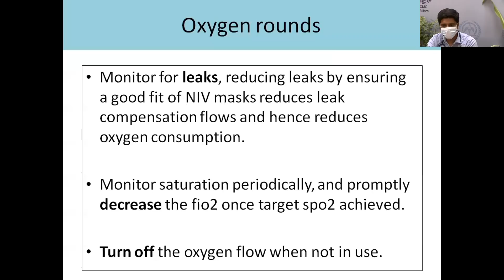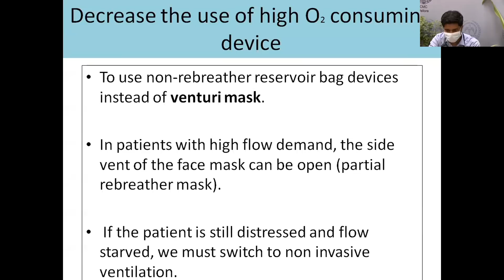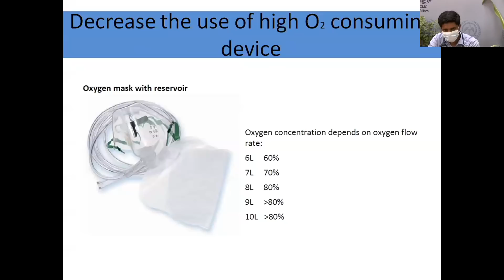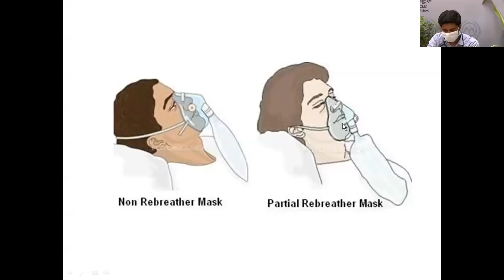So we have moved on from the Venturi mask, which is a high oxygen consuming device, to a non-rebreather reservoir bag device, where with a flow rate of 6 liters we can achieve 60% FiO2, as compared to the Venturi mask, which will require a flow rate of about 15 liters. In patients with high flow demand, the side vent of the face mask can be opened up so that it acts as a partial rebreather mask, so that flow starvation doesn't occur. If the patient is still distressed and flow starved, we must move on to non-invasive ventilation. So this is a picture of the NRM, where, as you can see, 6 liters can give a FiO2 up to 60%, 8 liters up to 80%. And this is how the NRM mask can be converted to a partial rebreather, where once you remove the valve over here, it acts as a partial rebreather mask, so flow starvation doesn't occur.